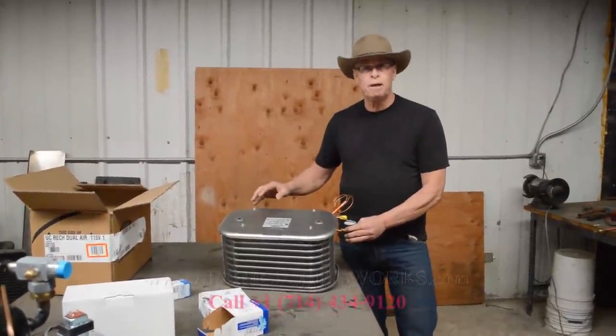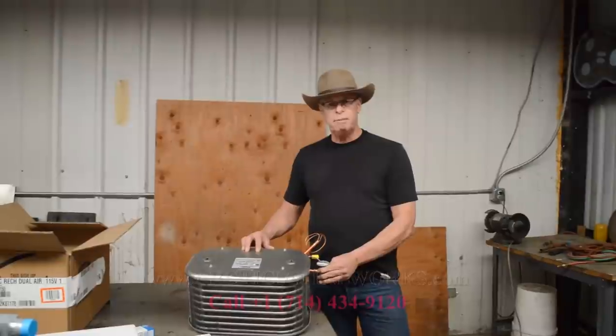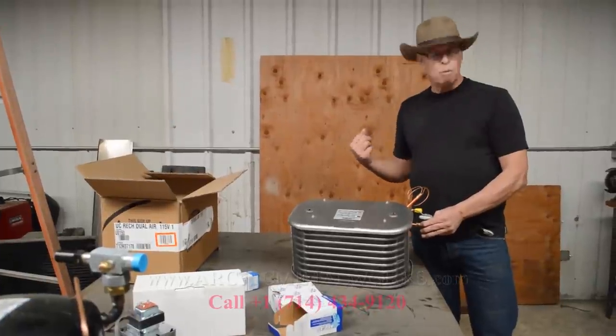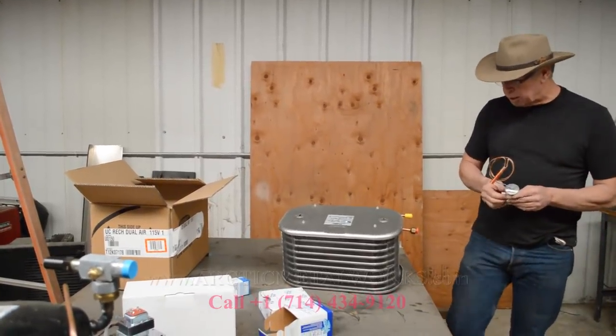So it's the process of going from liquid to vapor — less dense — that makes it go cold? That's right. That transfer takes place and that's what makes it able to absorb the heat that's in the room that we're trying to remove and take outside to the condensing unit. When the Freon goes through this coil it's cold — it's frosting the pipes — and there's a fan inside blowing across that. I don't want to say it's blowing cold air into the room — I want to say it's removing the heat from the room by absorbing it into the Freon, which is then carried via this pipe back to the outdoor unit.